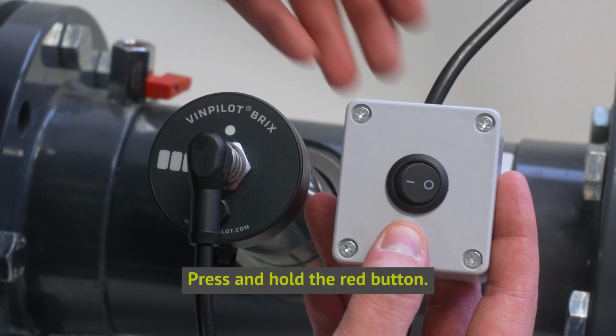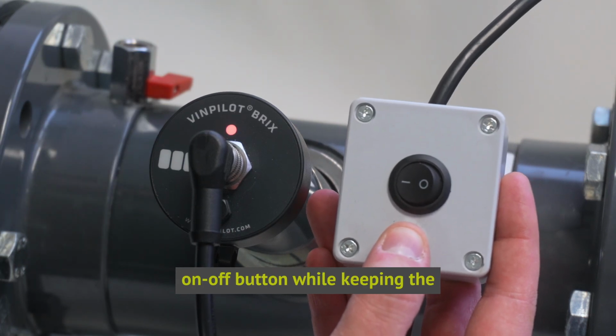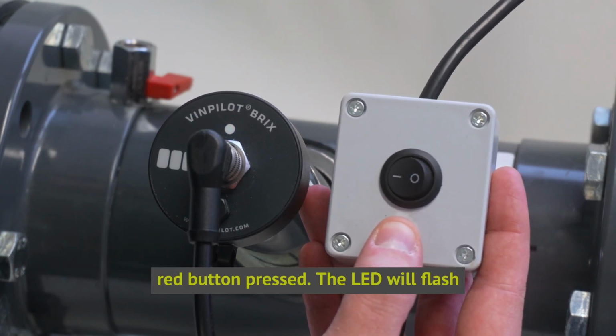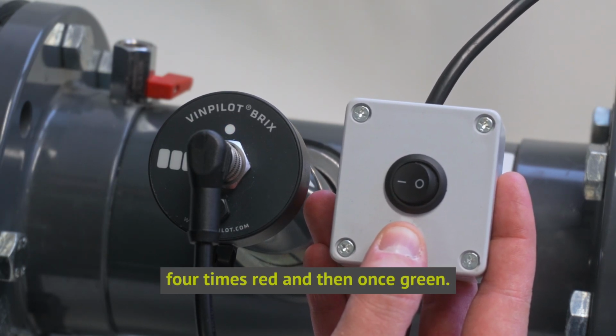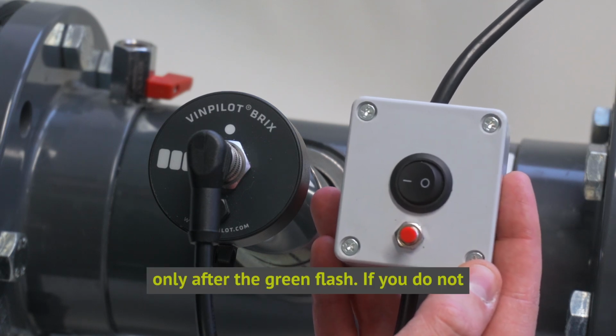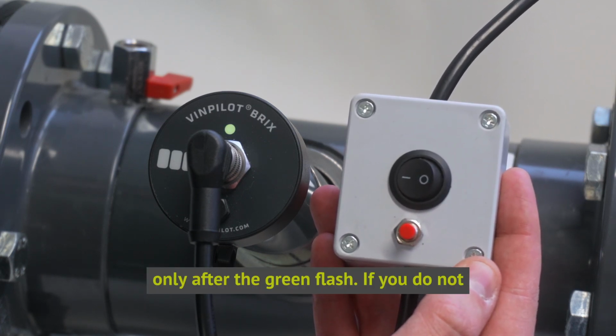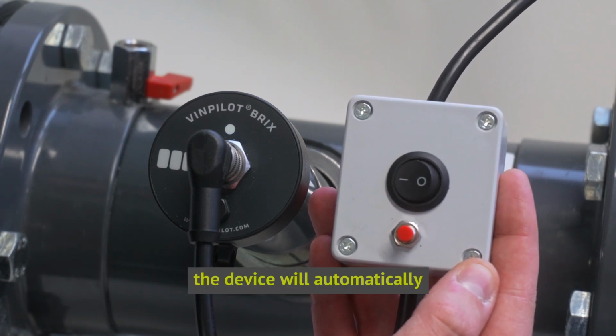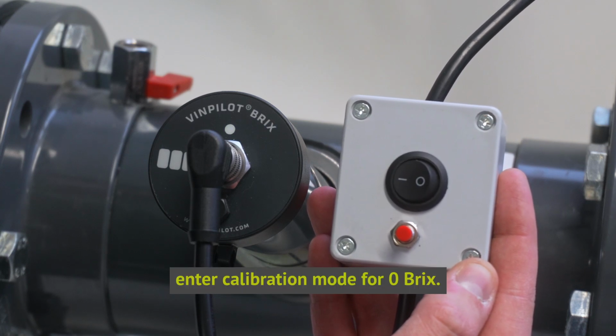Press and hold the red button. Switch the device on using the on-off button while keeping the red button pressed. The LED will flash 4 times red and then once green. Release the red button only after the green flash. If you do not press the red button again, the device will automatically enter calibration mode for 0 Brix.